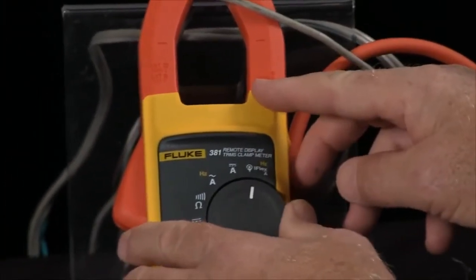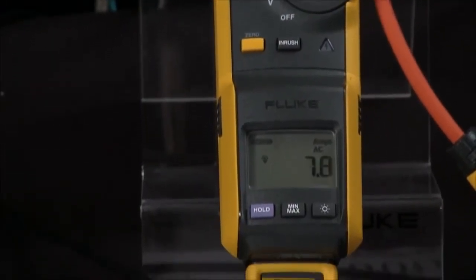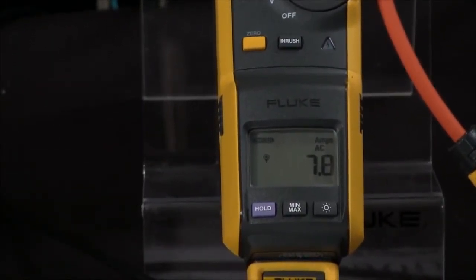Then we change our display over to the iFlex, hit the inrush key and start our motor, and we can get the inrush current.